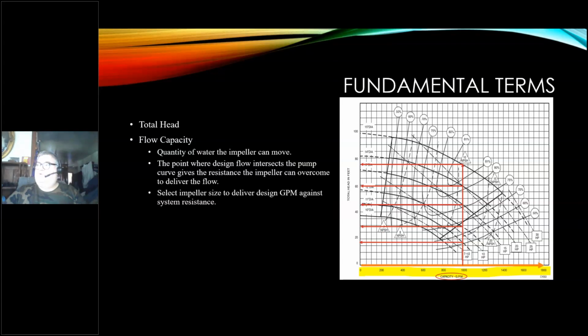The higher the head, the less the flow. That pump can only pump against a certain resistance. If you notice, on our first line there for the 15-inch diameter, it falls right in line with the best efficiency also. We'll talk about that in a moment. But you want to select the impeller size to deliver the design GPM against your system resistance. So if you design the system against a certain resistance, then you're going to select a pump that will pump the right amount of flow against that resistance.